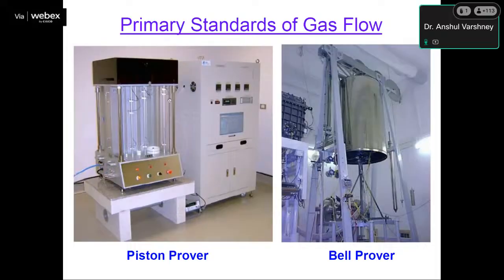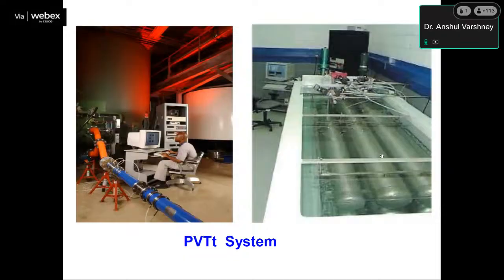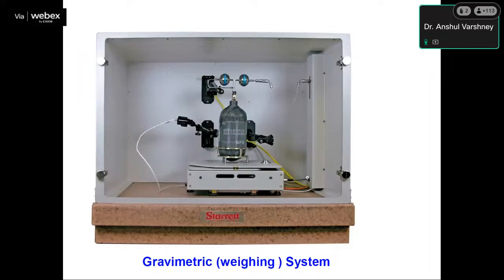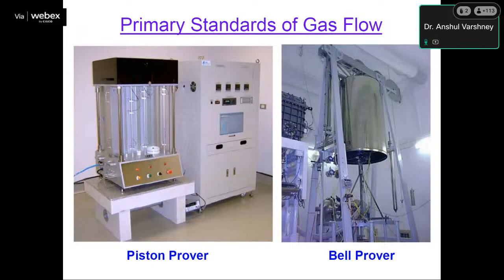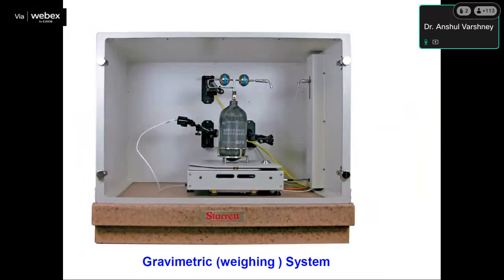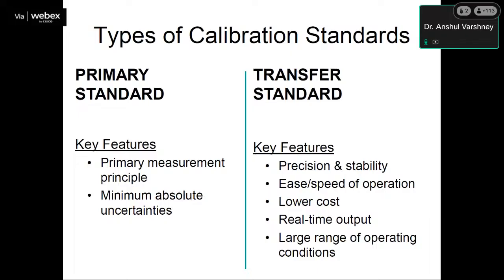So this is the piston prover. These are the other standards for gas flow. Primary standards like the piston prover and bell prover. This is basically a PVTT system. This is the NIST USA PVTT system, and gravimetric systems. However, the major disadvantage of the piston prover, bell prover, and gravimetric system is that whenever you purchase these readily available systems and any problem is encountered, you are dependent on the manufacturer or service provider. However, if you develop the primary standard completely by yourself, there is no problem of dependency on others. You can rectify the problem in-house easily.